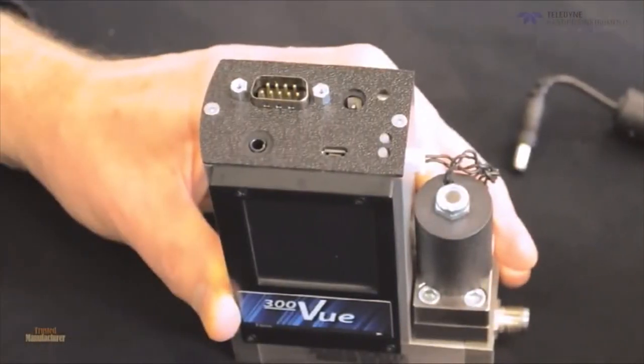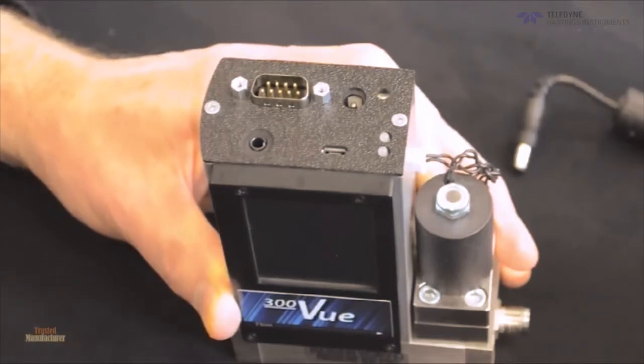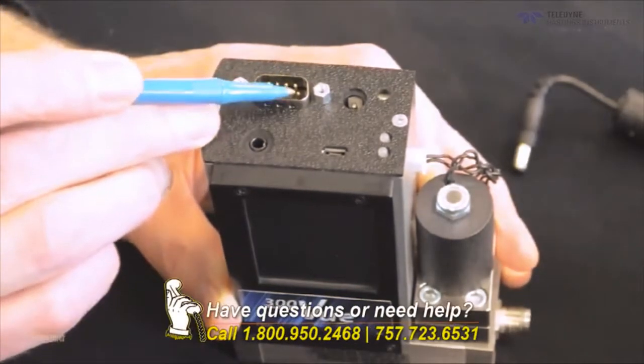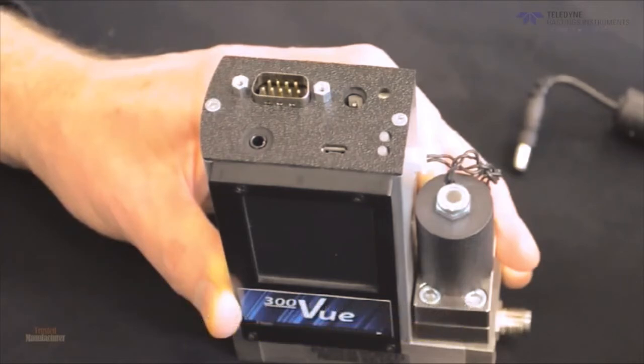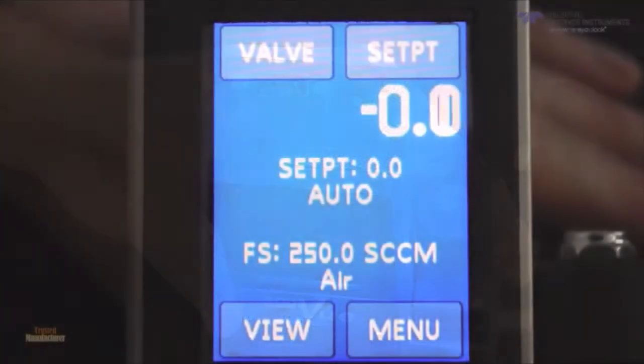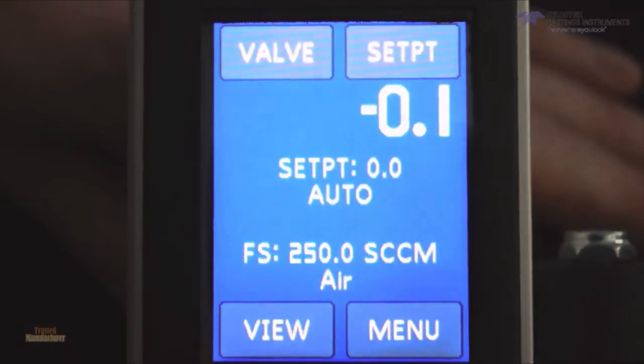The 300 Vue has an external input pin number 1 right here, which can accept an analog pressure transducer signal. So this is very flexible. We can take in a 0 to 10 volt, 0 to 5 volt, 0 to 20 milliamp, or 4 to 20 milliamp signal. And it can be either positive pressure or vacuum. Now, we can send our command signal using the same type of analog signal. Let me show you how quickly and easy it is to set up the configuration on the 300 Vue.